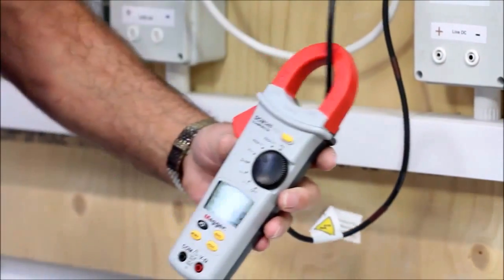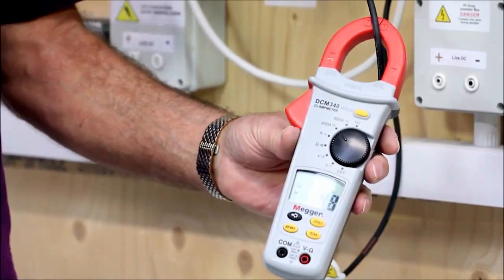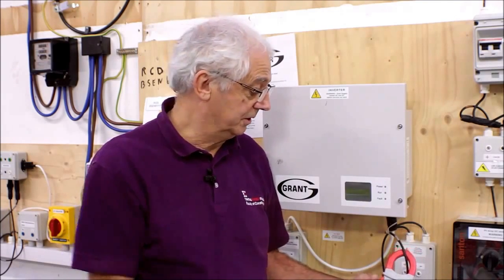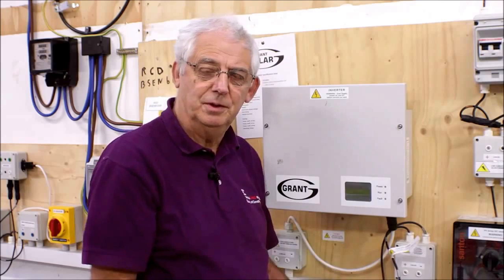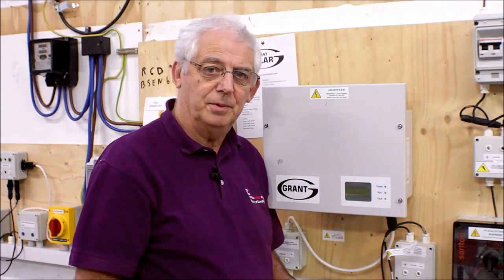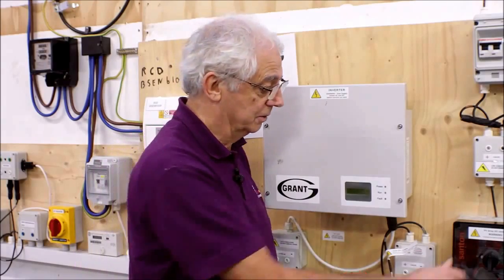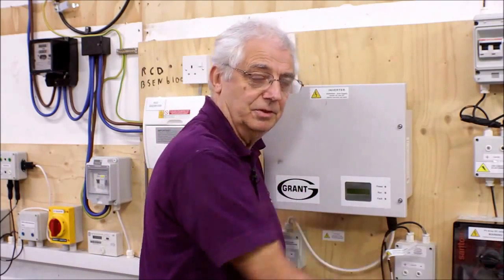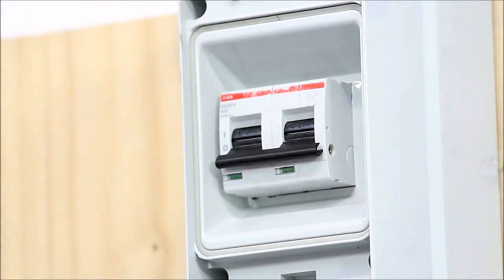And there we are, we can see that the measurement I'm getting is indeed 4.8. So that's just showing me that my system is working as well as I could expect it to be. The thing I need to remember now, of course, is because this is a DC system, when you pull the leads apart under load, you're going to end up with a big arc. So I really need to make sure I isolate this first. Once it's isolated, I can then disconnect it and reconnect the inverter.